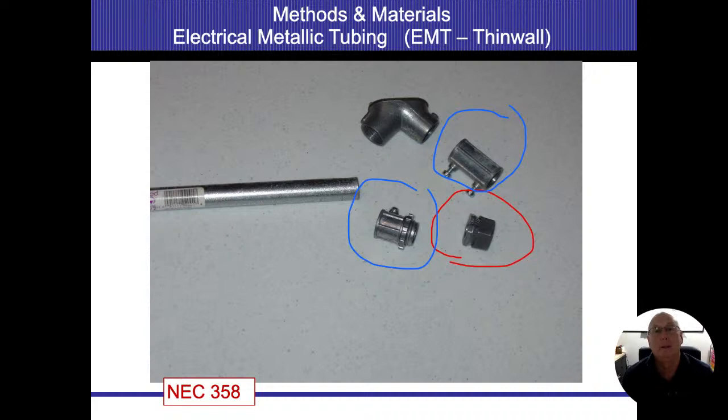It's going to be really difficult to pull too many wires through this stuff. You're going to end up damaging the wires. So once it comes through, we see them damaged. Those are usually the things that we end up calling out. But it can be done. You can't pull too many through it. And then the pipes themselves are going to be hot.